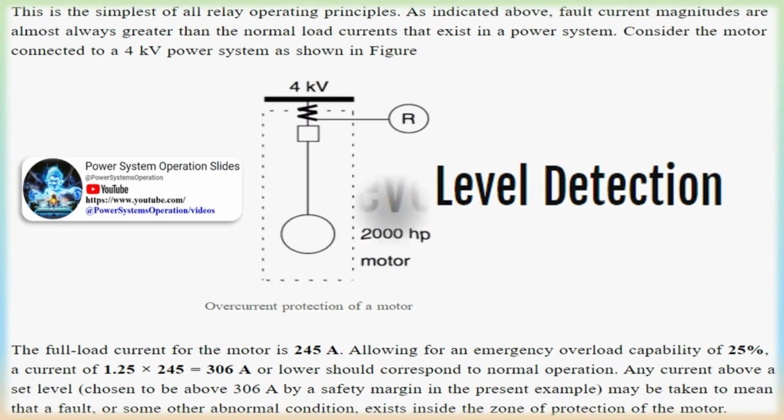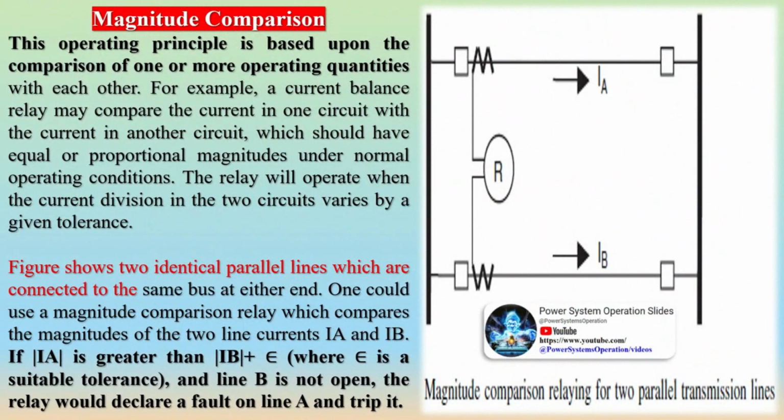If one were to use the magnitude of a fault current to determine whether some action should be taken, it is clear that a fault on the inside, fault F1, or on the outside, fault F2, of the zone of protection is electrically the same fault, and it would be impossible to tell the two faults apart based upon the current magnitude alone. Much ingenuity is needed to design relays and protection systems which would be reliable under all the variations to which they are subjected throughout their life.